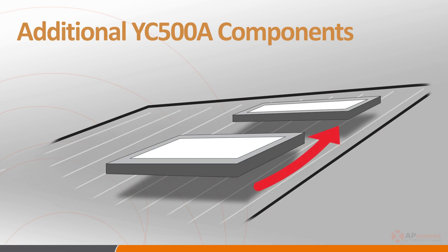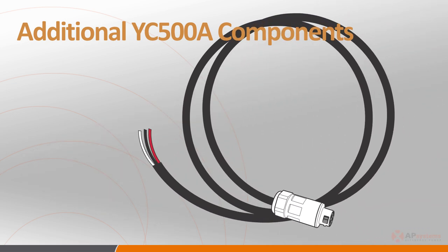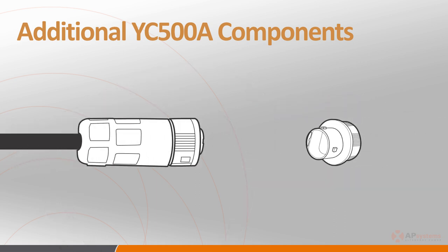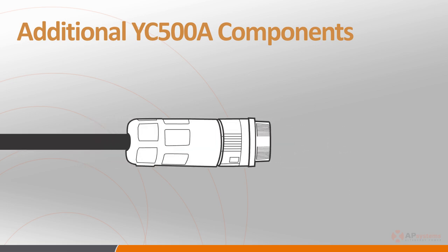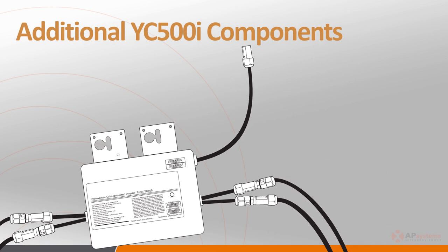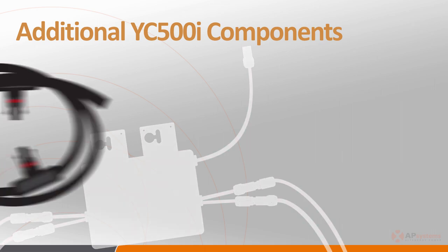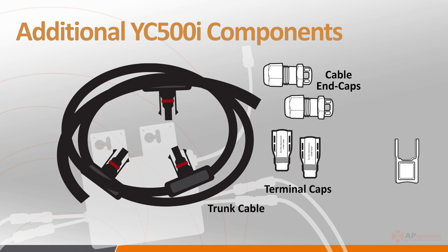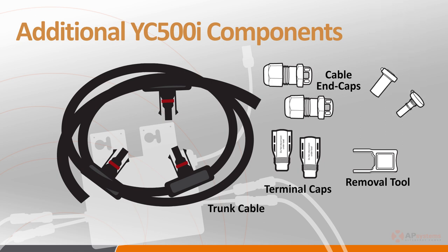The AC branch cable ends have a female connector at one end for attaching to the first YC500 in a circuit, and bare wires — red L1, black L2, and white neutral — at the other end for connecting into a junction box. The end caps are weatherproof termination caps that lock onto the last YC500 female AC connector in the circuit as protection against the elements. For the YC500I, additional components include an AC bus or trunk cable, cable end caps to seal off an open end of the trunk cable, terminal caps to seal off an unused drop on a branch, a removal tool to remove the terminal sealing cap, and MC4 caps for unused DC cables on the microinverter.